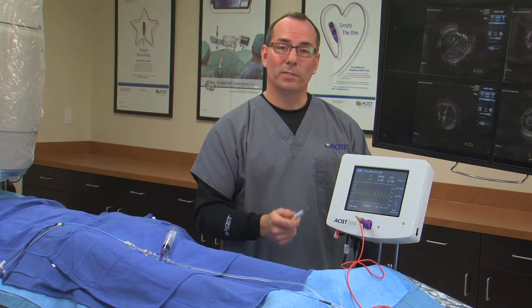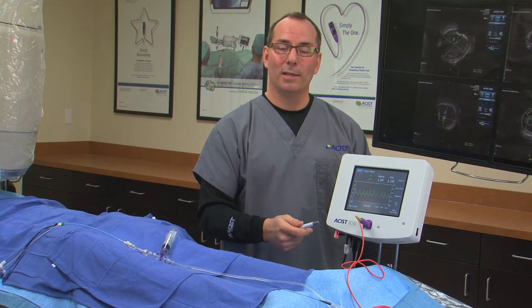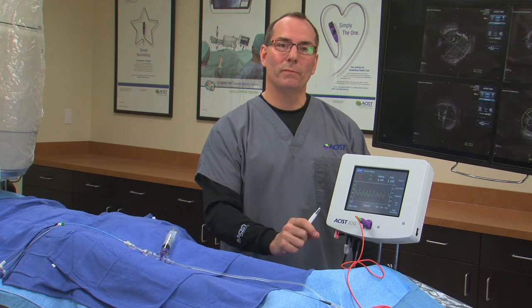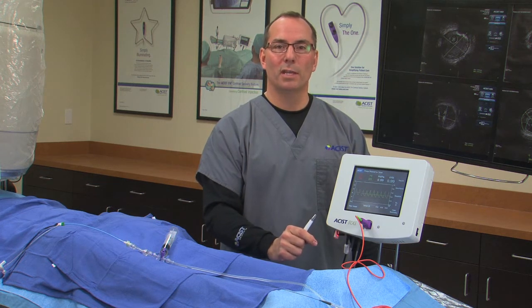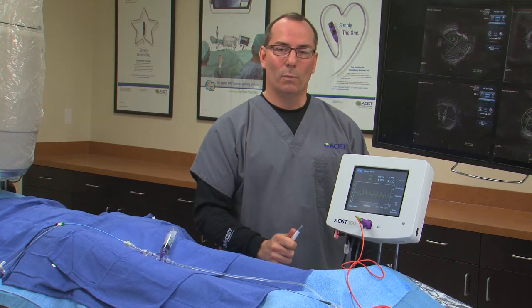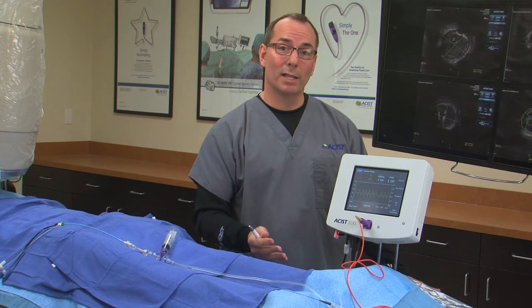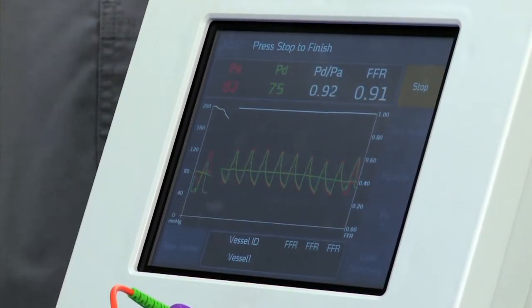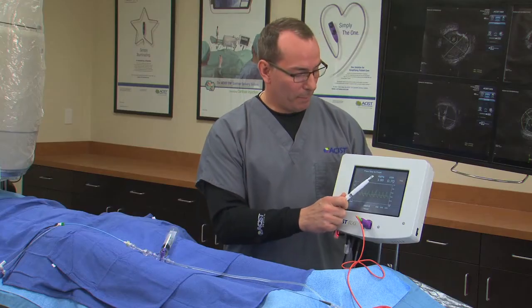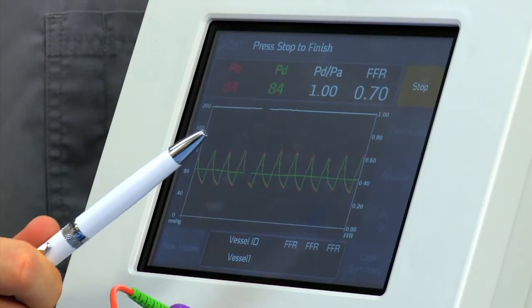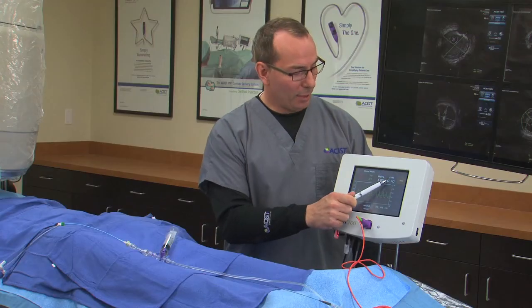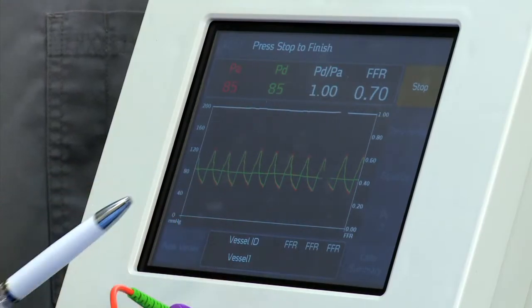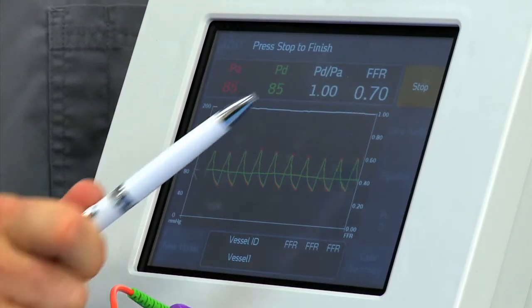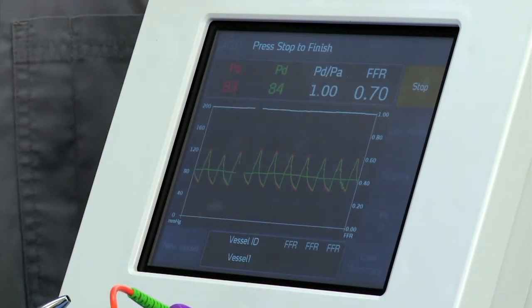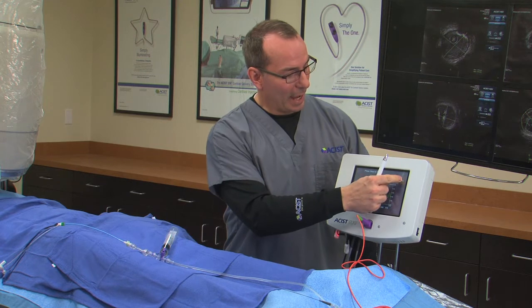Now, with the physician's wire of choice in the body, we can simply advance that transducer inside the coronary artery to the area of interest, and we're ready to start adenosine. Once the patient gets that hyperemic response of the adenosine, we can simply hit record on the screen and we'll record that hyperemic response. You can see how the PD-PA ratio was tracking the FFR the entire time. And when the FFR got to be the lowest, the system seeked out that value and placed that here under FFR. We're going to stop the recording.